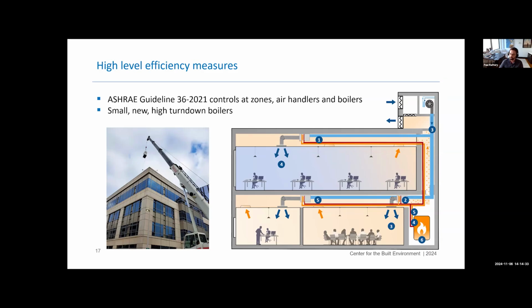So this was not like a typical retro-commissioning exercise where you only touch the boiler plant or you maybe fix the supply air temperature set points on the air handler. We went to every single zone in the building and corrected the set points and the controls and did that iteratively over a year to make sure everything was tuned correctly. So this was a much larger effort than is normally undertaken in a retro-commissioning project. But we didn't actually have to replace the physical controller hardware. So this is all just software changes on the building automation system, right?